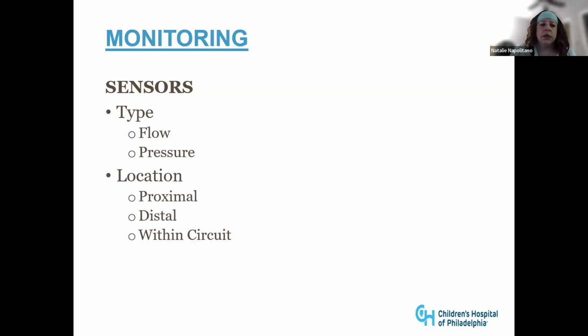And then the location of the flow sensors is also an important piece, whether they're proximal or distal or within the circuit. If they're within the circuit, it can actually be fairly accurate for those that have used the LTV ventilator with their very big tubing. They didn't have small tubing because it didn't matter. Their flow sensors were right within the Y of the ventilator circuit, and they were fairly accurate, particularly with triggering, even with very small children.